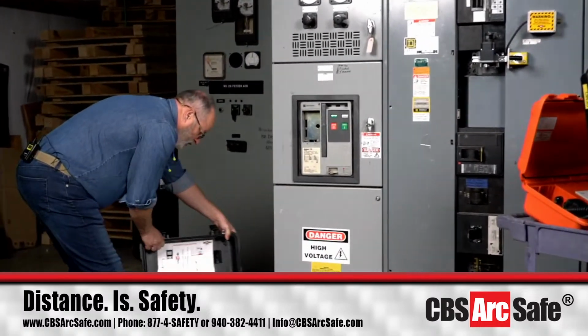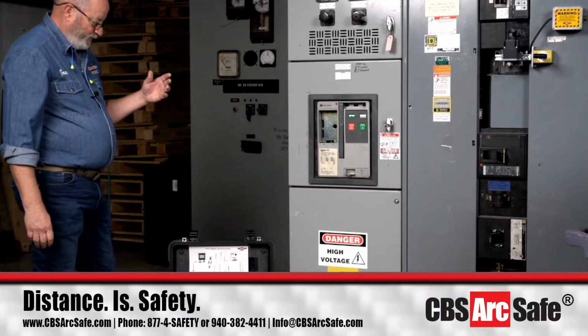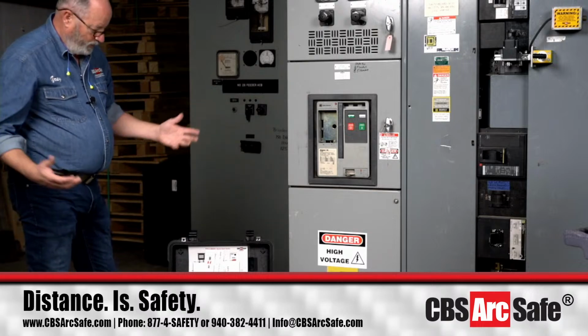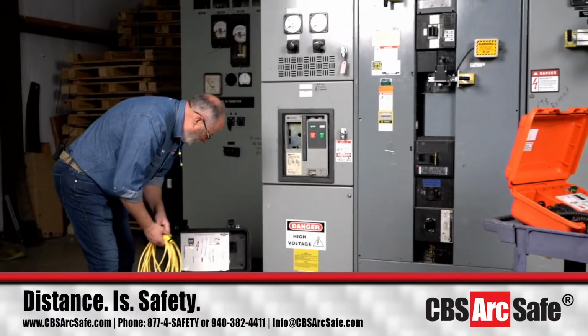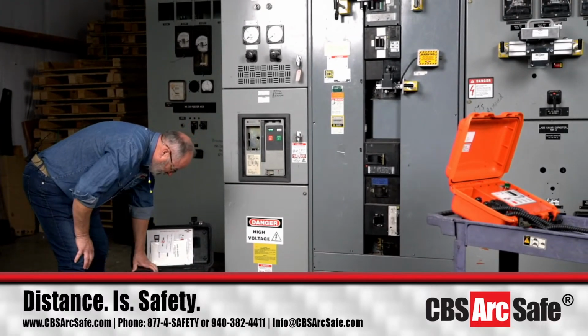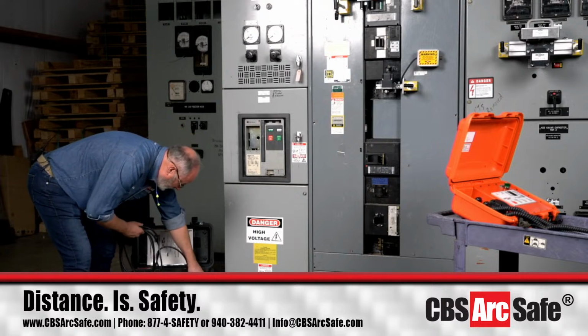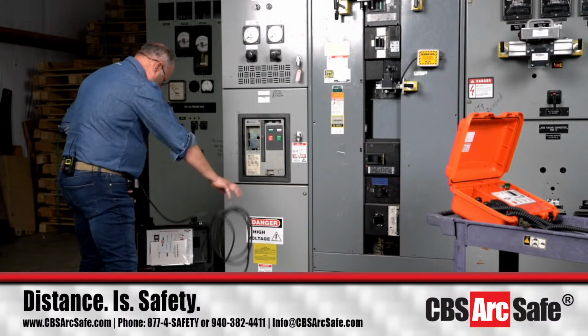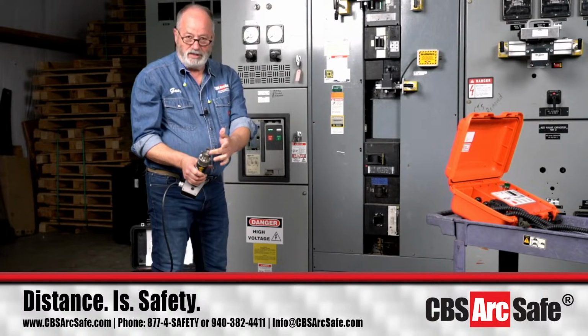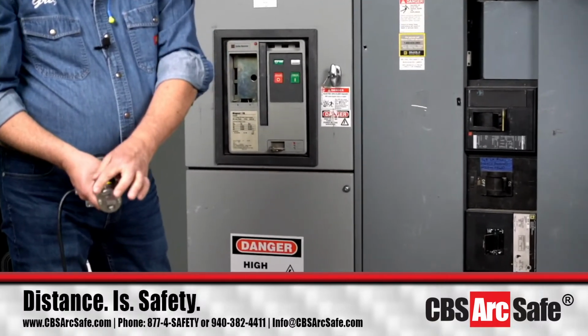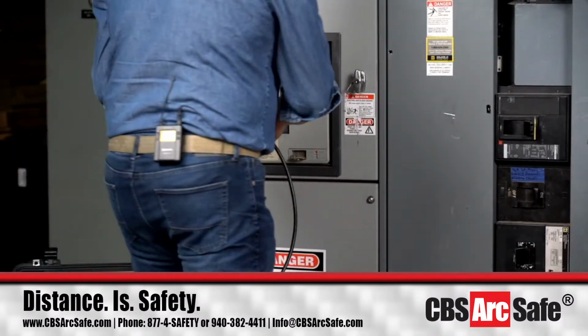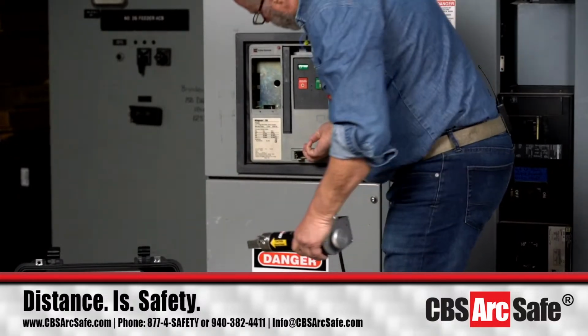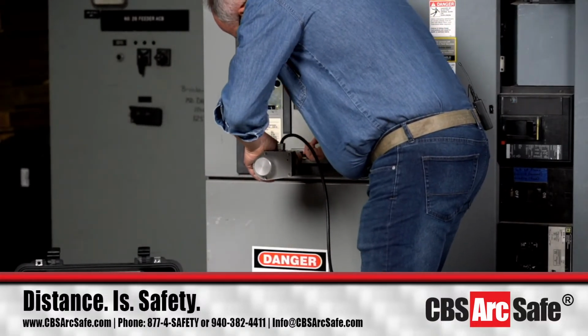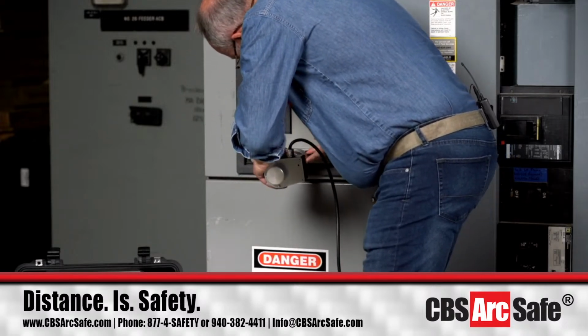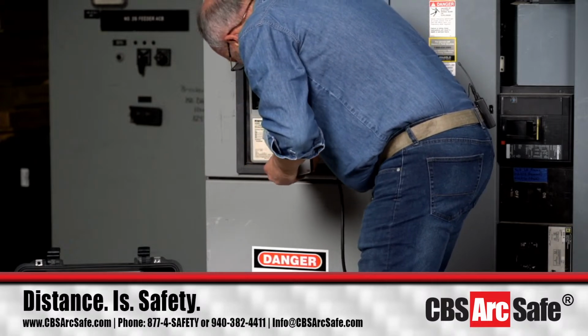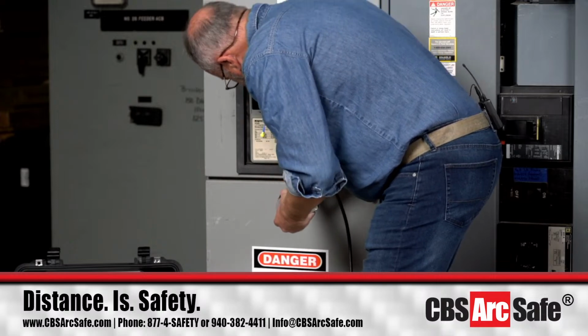The last thing we're going to do with our Magnum DS breakers is rack it. This is the updated version of the MDSR1 for remote racking, and it actually has a Milwaukee M18 battery for power, so we can use this and be away from it. This hooks into the lockout, tagout, and racking mechanism. This is our anchor that moves it and locks it into place. I lift the port here, insert it right into there, lift up the little hook, and get this thing in. Let me check how close I am to the orientation here.